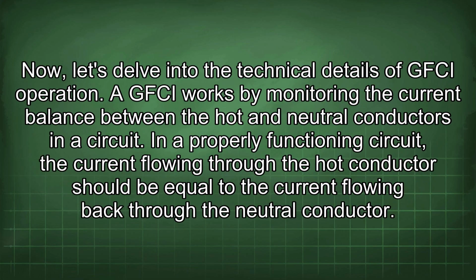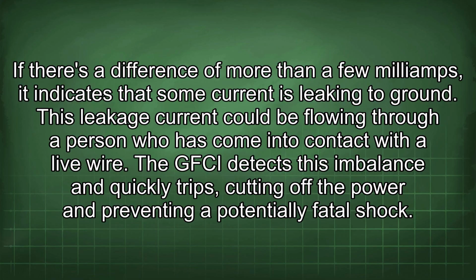Now let's delve into the technical details of GFCI operation. A GFCI works by monitoring the current balance between the hot and neutral conductors in a circuit. In a properly functioning circuit, the current flowing through the hot conductor should be equal to the current flowing back through the neutral conductor. If there is a difference of more than a few milliamps, it indicates that some current is leaking to ground.